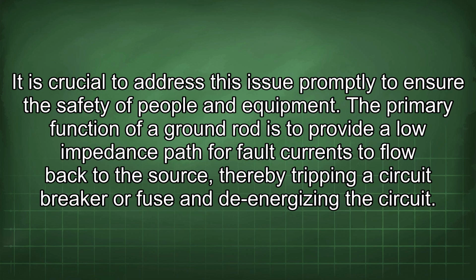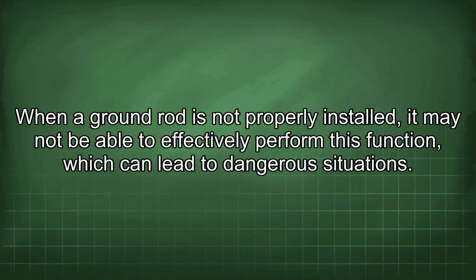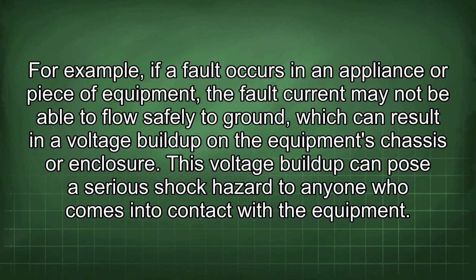The primary function of a ground rod is to provide a low impedance path for fault currents to flow back to the source, thereby tripping a circuit breaker or fuse and de-energizing the circuit. When a ground rod is not properly installed, it may not be able to effectively perform this function, which can lead to dangerous situations. For example, if a fault occurs in an appliance or piece of equipment, the fault current may not be able to flow safely to ground, which can result in a voltage buildup on the equipment's chassis or enclosure. This voltage buildup can pose a serious shock hazard to anyone who comes into contact with the equipment.